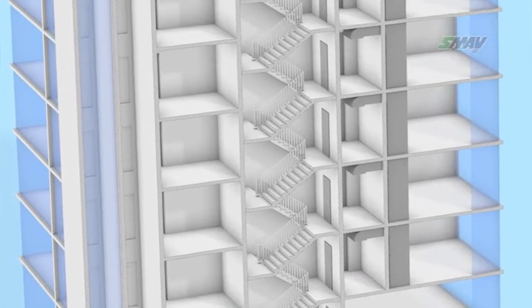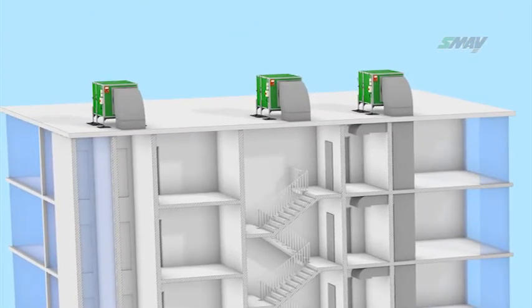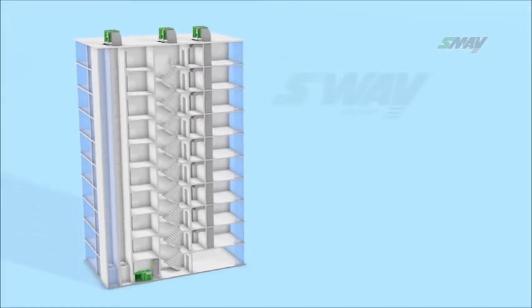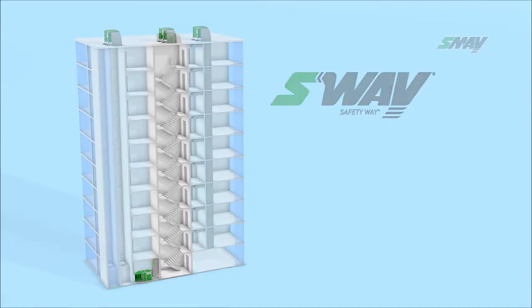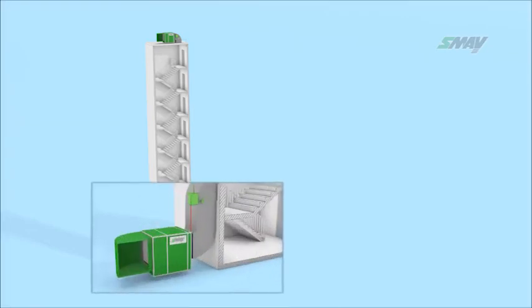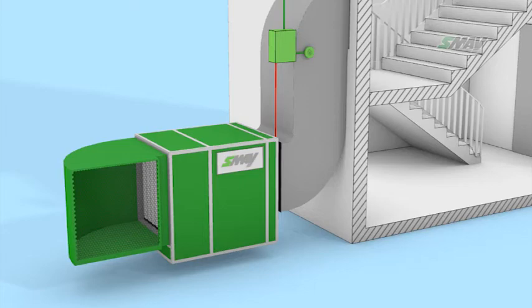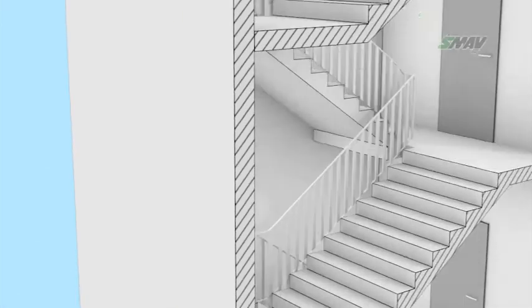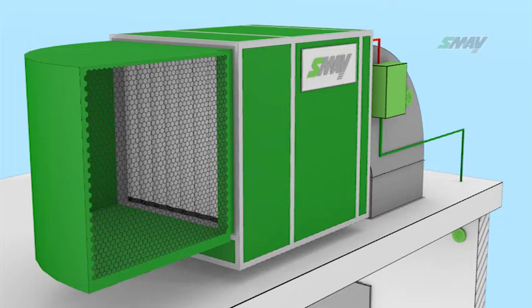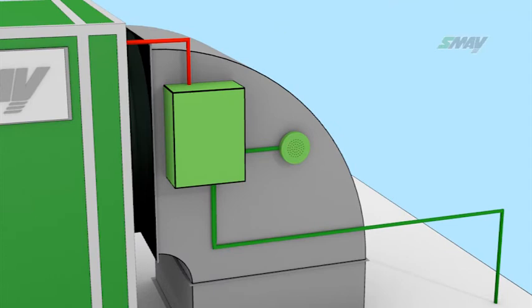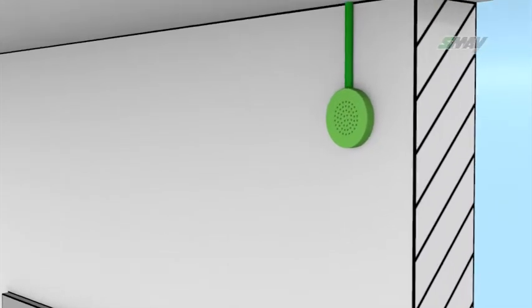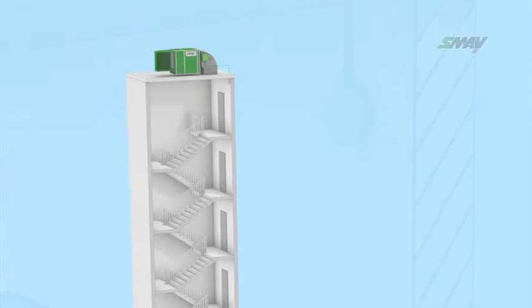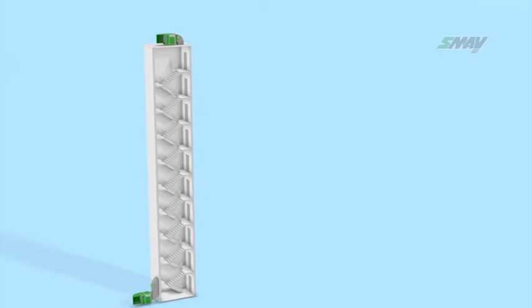Regardless of the required PDS pressure differential system class, SMAY suggests using the safety way pressure differential system. The basic version comprises two reversible flow fans located at the extreme floors of the stairwell, working in opposite directions — when one delivers air to the stairwell, the other extracts it. The fans are equipped with motorized air dampers operating as pressure controllers and a regulation automation system, creating a volume of controlled airflow at a controlled intensity, resulting in a stable distribution of static pressure across the entire stairwell.